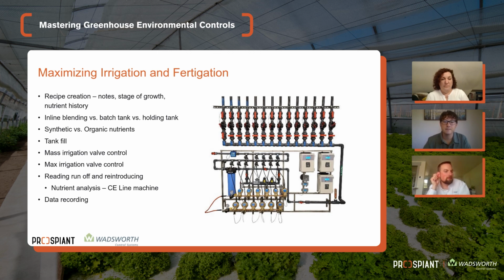The biggest thing here is comparing these modern inline systems to the old style - I'll call it a dummy machine that's a pumper or doser that doesn't collect any data. It might have an instantaneous readout, but it's a separate standalone machine collecting nothing. It's hard to go back and gauge what you were doing last season, last crop, or last rotation. We still go into greenhouses all the time and see those rudimentary systems with no link to the climate control system, so they're not working in unison most times, and there's no ability to really monitor that system. Yeah, you have the real-time reading, but other than that you don't have much.